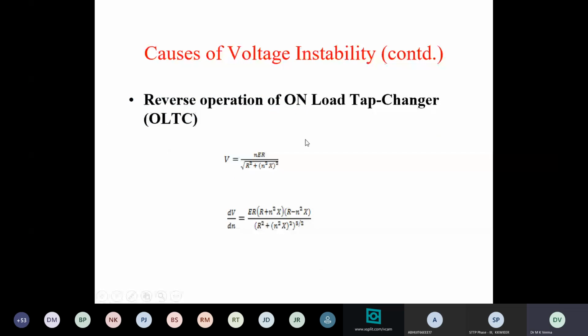Reverse action of OLTC may also cause voltage instability. What is the OLTC doing? For an OLTC, the taps are provided on the high voltage side. Suppose the voltage goes down, you have to move the tap downwards so that you increase the turns ratio, and with the increase in turns ratio, we are able to increase voltage. It means for normal operation of the tap changer, the sensitivity of voltage magnitude with respect to turns ratio should be positive. That is, dV by dN should be positive. With an increase in turns ratio, the voltage should increase. But if with an increase in turns ratio the voltage decreases, then control will fail. It will cause deterioration of voltage. So instead of controlling the voltage, it will deteriorate the voltage. That is a case of voltage instability.